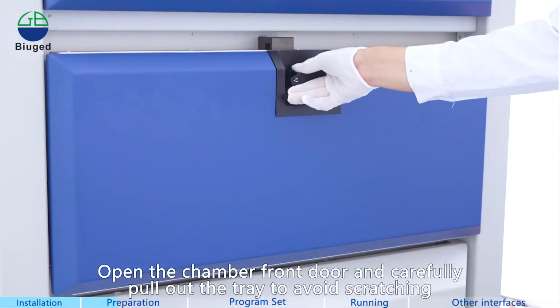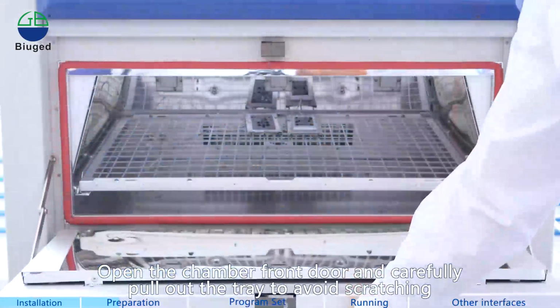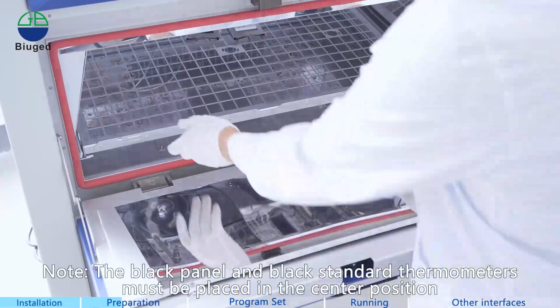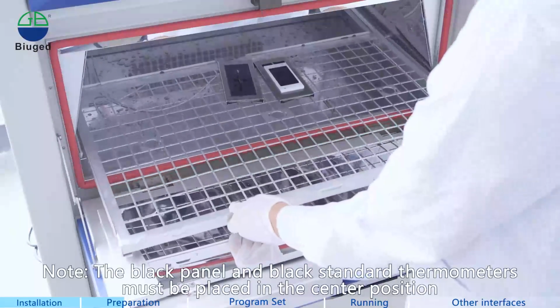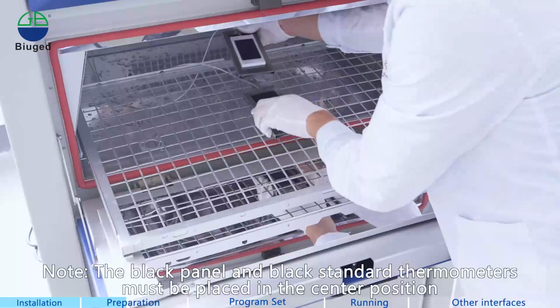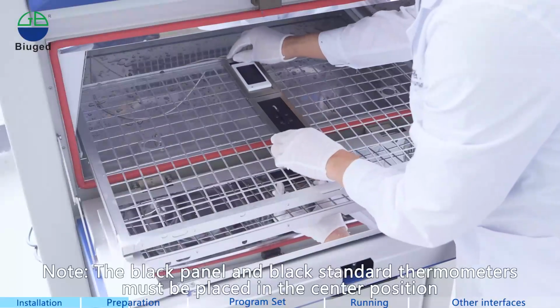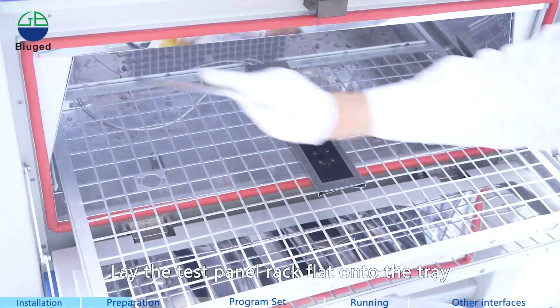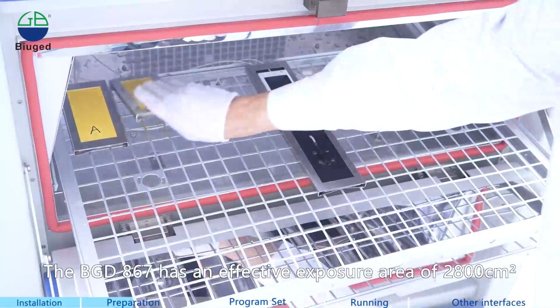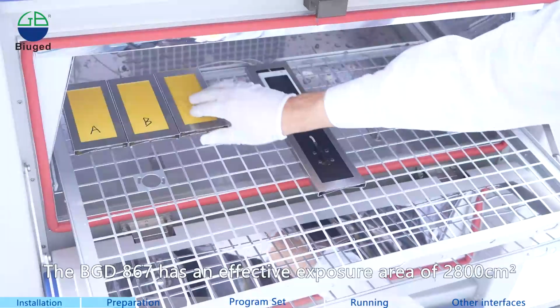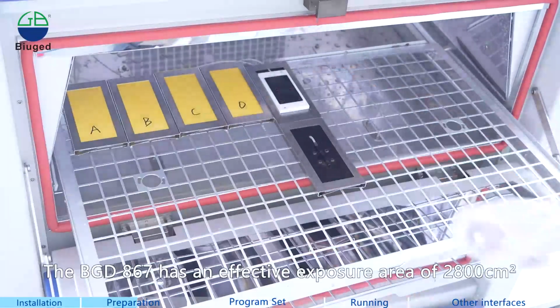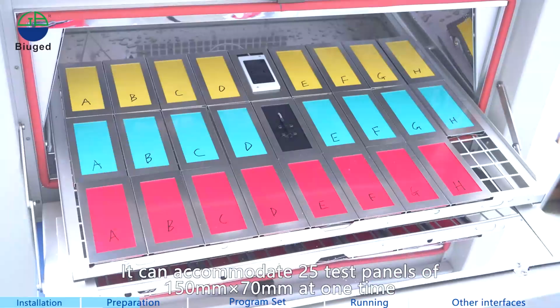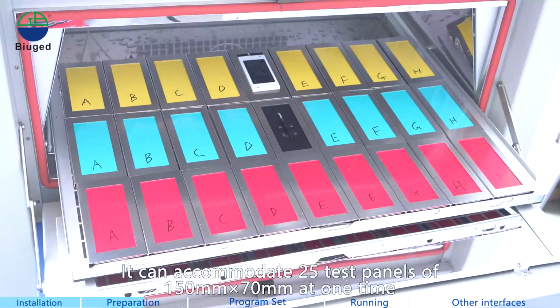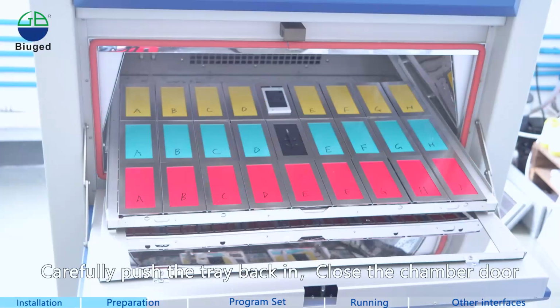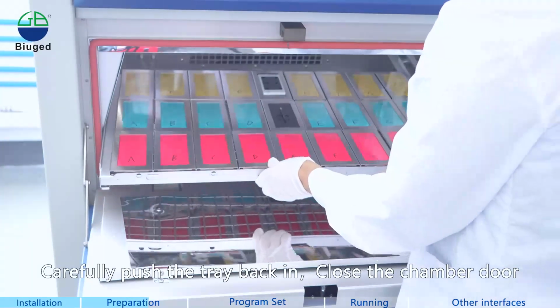Open the chamber front door and carefully pull out the tray to avoid scratching. Note, the black panel and black standard thermometers must be placed in the center position. Lay the test panel rack flat onto the tray. The BGD 867 has an effective exposure area of 2,800 square centimeters. It can accommodate 25 test panels of 150 mm x 70 mm at one time. Carefully push the tray back in, close the chamber door.